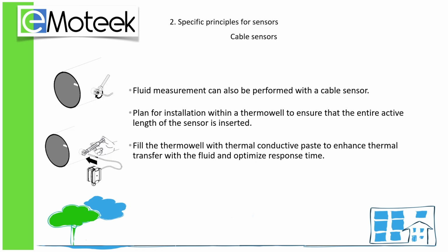Now let's move on to specific principles. Let's start with cable sensors. You should know that fluids can also be measured with a cable sensor. Mount it inside a thermal well to insert the entire active length.